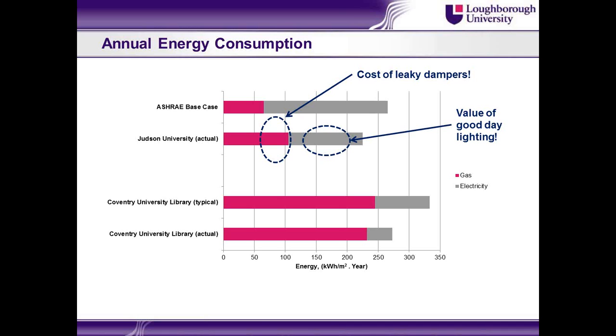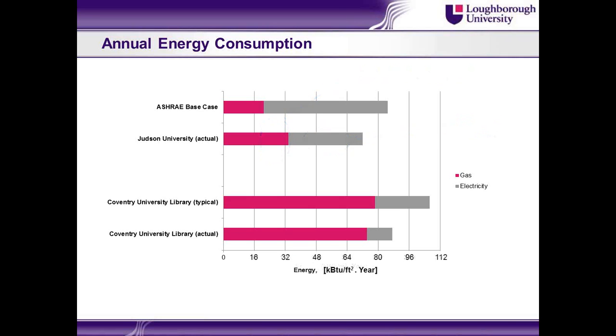And here we've got a reduction in the electricity consumption because we feel that the daylighting strategy for the building was so successful. Having the daylight-linked luminaires, we were able to dim those around the light wells and therefore reduce the energy consumption of electricity. Coventry University Library was the benchmark we were working to at the time, and we showed about a 10-15% reduction in the energy consumption, again due to the good daylighting strategy for that building. There's also some reduction in the gas, as you might expect, because of those good U values, high insulation values, etc. I've just put the imperial units there at the bottom.